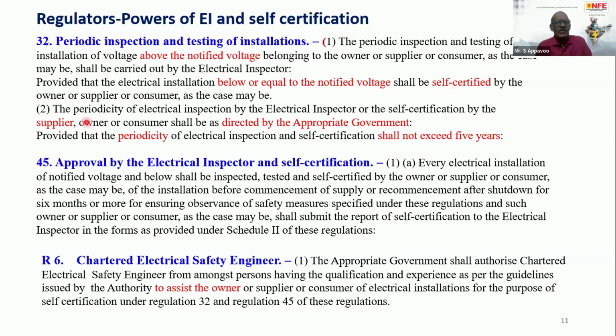Whatever the periodicity may be, of electrical inspection by the electrical inspector or self-certification by the supplier, owner, or consumer, self-certification applies to the supplier, owner, or consumer. Who has to certify it? The chartered electrical safety engineer. So every installation has to be either inspected by the electrical inspector or certified by a competent electrical safety engineer, and the periodicity shall not exceed 5 years. This is the base: every citizen is given the opportunity, the right, to ensure electrical safety in his installation through these measures. After the initial supply, they have to go for another inspection if there are any additions or expansions in the premises. This is governed under Regulation 45.